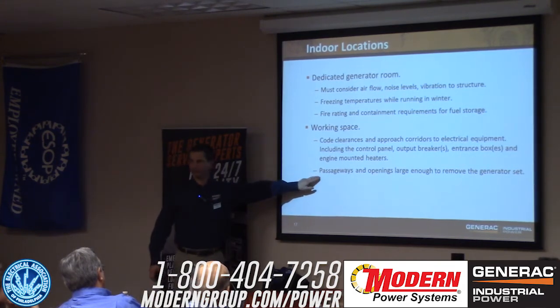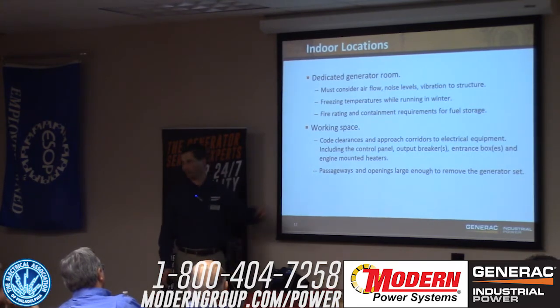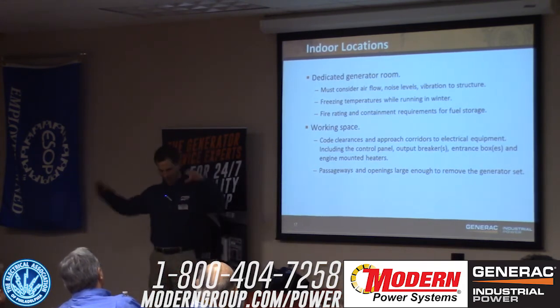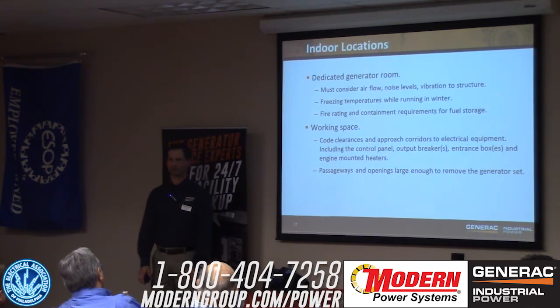At some point in the distant future, 20 to 25 years down the road, somebody's going to want to replace that genset. Did you put layers of floor and roof over it such that the only way that machine is coming out is in pieces? I just did that up in Massachusetts. I've got a project going on in Washington, D.C. right now where they're fixing to plant a 500 kW genset two floors below grade. I have no idea how they'll ever get it out when it needs replacing - but yeah, you're going to cut it up.